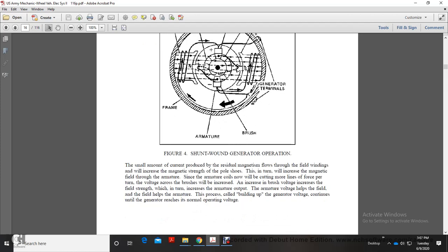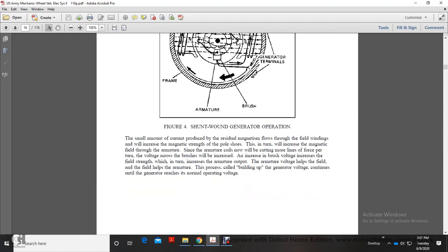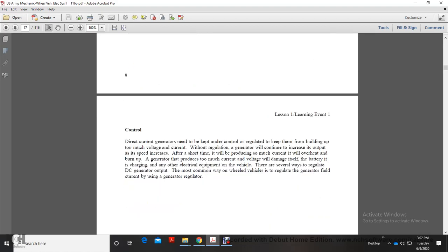The small amount of current produced by the residual magnetism flowing through the field winding will increase the magnetic strength of the pole shoes. This in turn increases the magnetic field, and the armature is now cutting more lines of force per turn. The voltage across the brushes will increase. The increase in brush voltage increases the field strength, which in turn increases the armature output voltage, helping the field. This process is called building up, and the generator voltage continues to build until it reaches the normal operating voltage.